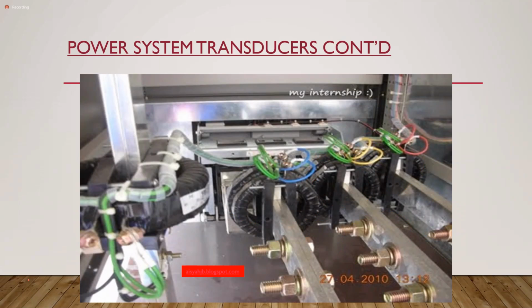Now, what we are looking at here seems to be set up for measurement. So the output of these CTs would then go to your meter, which would provide the measurement for revenue purposes. In terms of your CT characteristics, what you would get when you purchase a CT, and which you would use in your design circuit, you get the CT characteristics. And what I'm going to show you here, or the figure that you have, is a multi-winding CT.